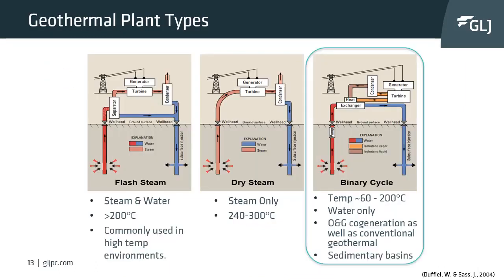There are three geothermal power plant types. Flash steam uses a combination of steam and water, usually at temperatures above about 200°C. Dry steam uses only steam produced directly from the ground, common near volcanic settings, with temperatures between 240 and 300°C. Binary cycle plants are becoming more common and can utilize temperatures as low as 60°C — common in oil and gas cogeneration and sedimentary basins. Hot water comes to surface, goes into a heat exchanger that vaporizes isobutane or an alcohol, which is then used to drive a turbine.